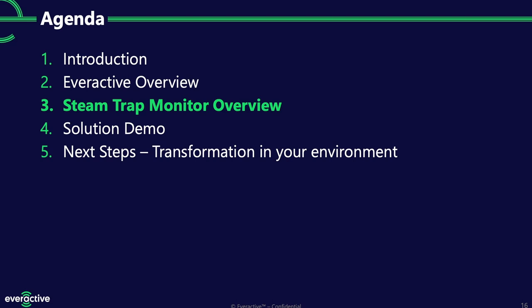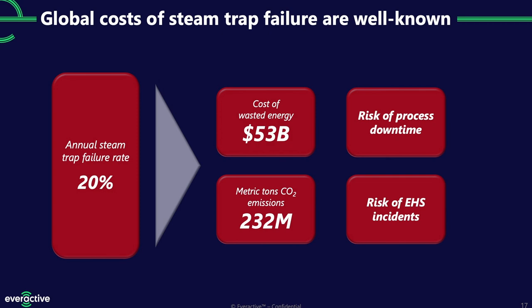Why start with steam traps? The Department of Energy says the annual failure rate on steam traps is about 20% — you're expected to lose roughly a fifth of your fleet each year. A friend at a steam trap manufacturer told me they're actually designed to fail — there are elements in them meant to be replaced over time. Globally, we see $53 billion in wasted energy annually and hundreds of millions of tons of wasted CO2 tied to steam trap failures.